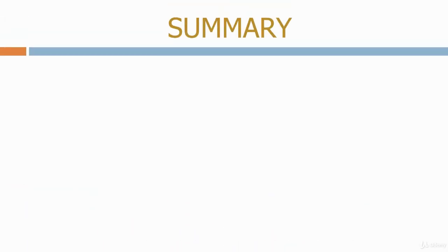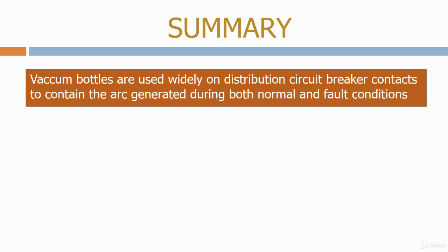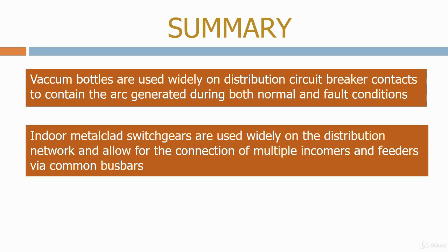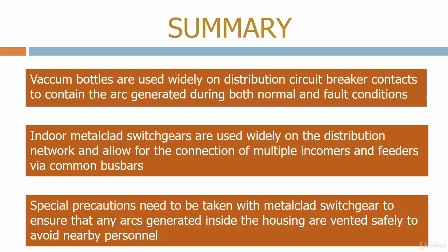Let's summarise what we've learned today. Vacuum bottles are used widely on distribution circuit breaker contacts to contain the arc generated during both normal and fault conditions. Indoor Metalclad switchgears are used widely on the distribution network and allow for the connection of multiple incomers and feeders via common bus bars. Special precautions need to be taken with metal-clad switchgear to ensure that any arcs generated inside the housing are vented safely to avoid nearby personnel.